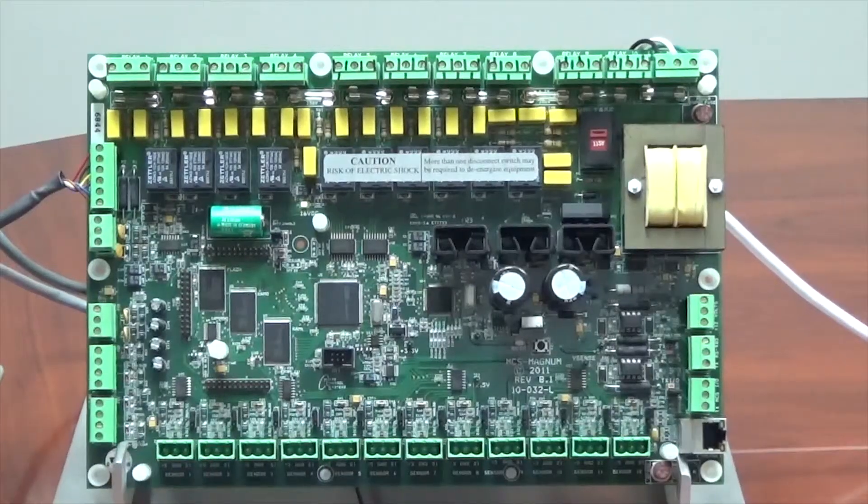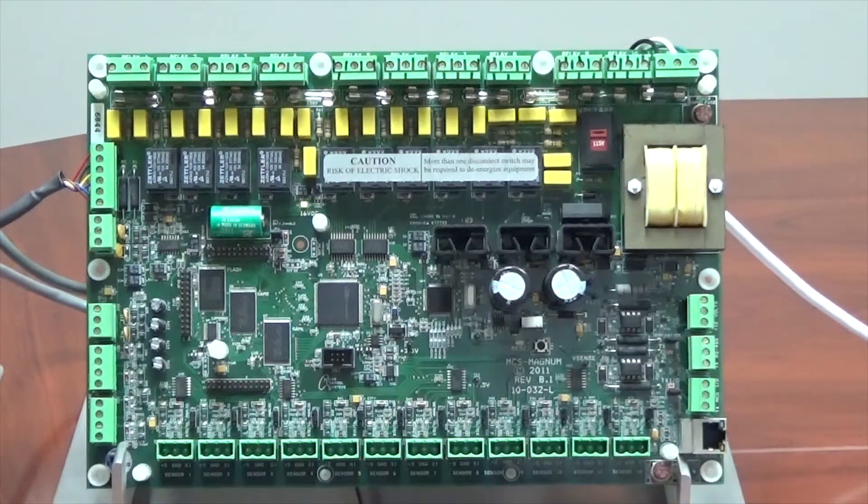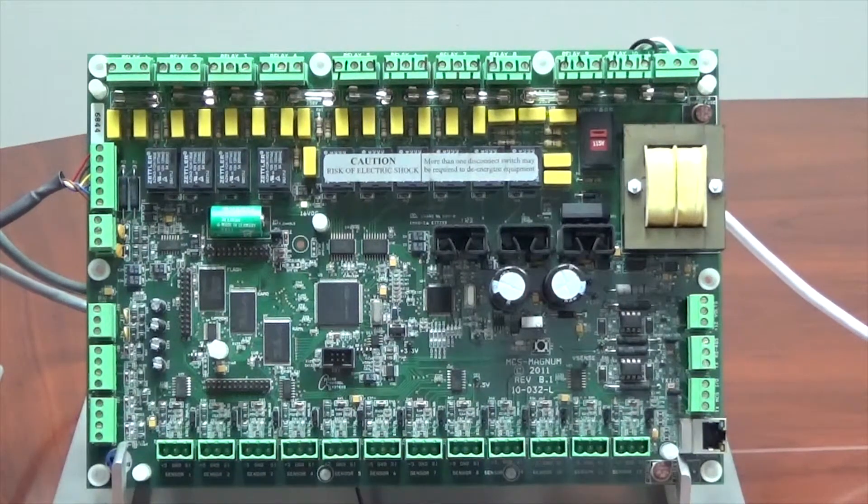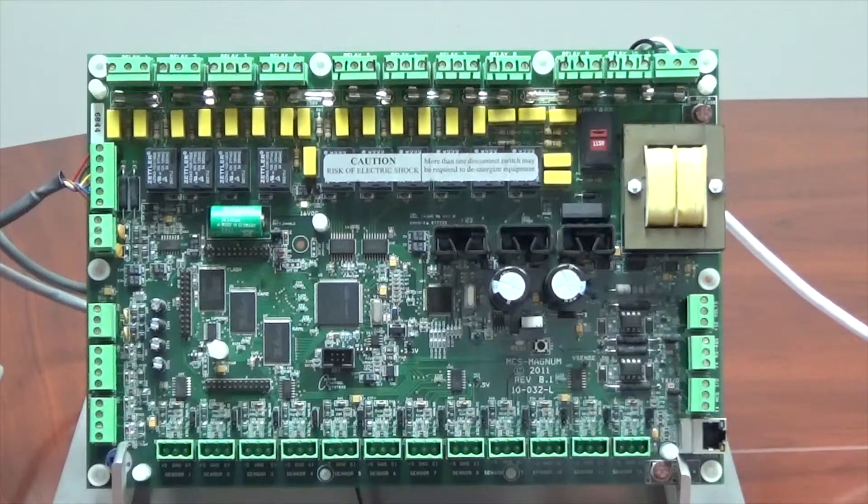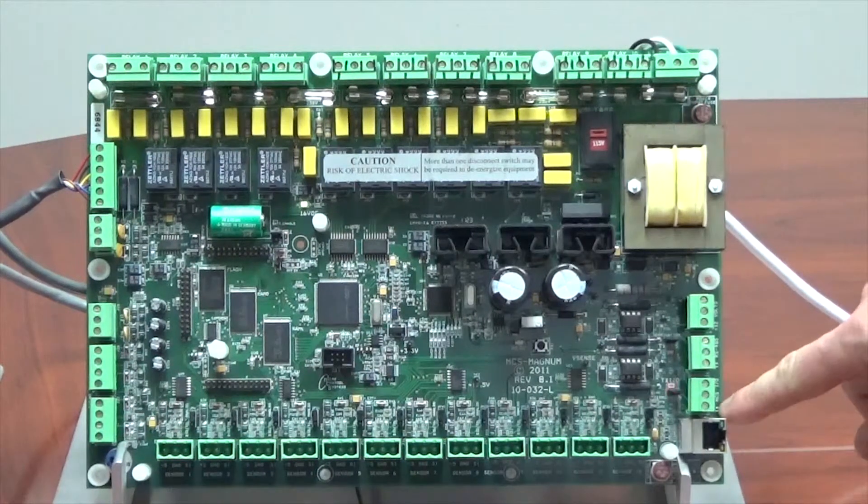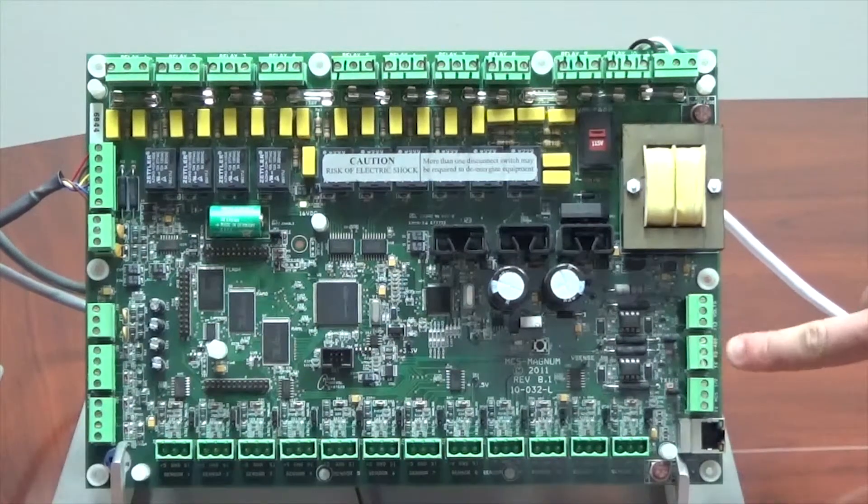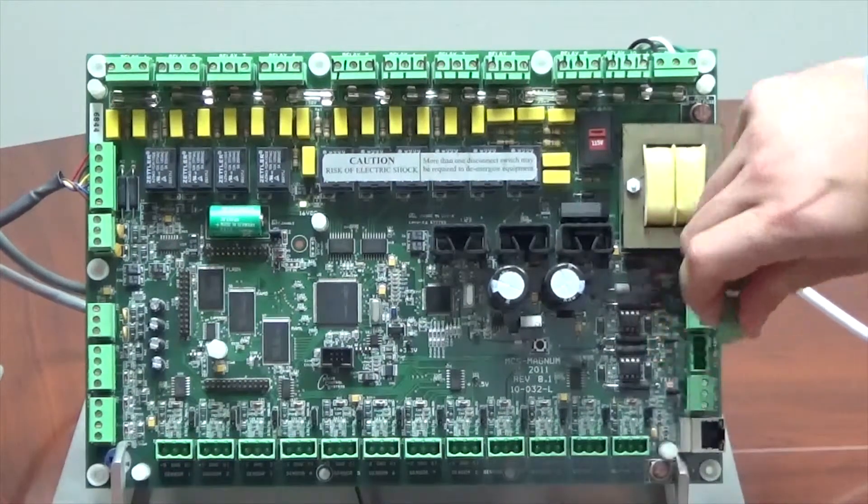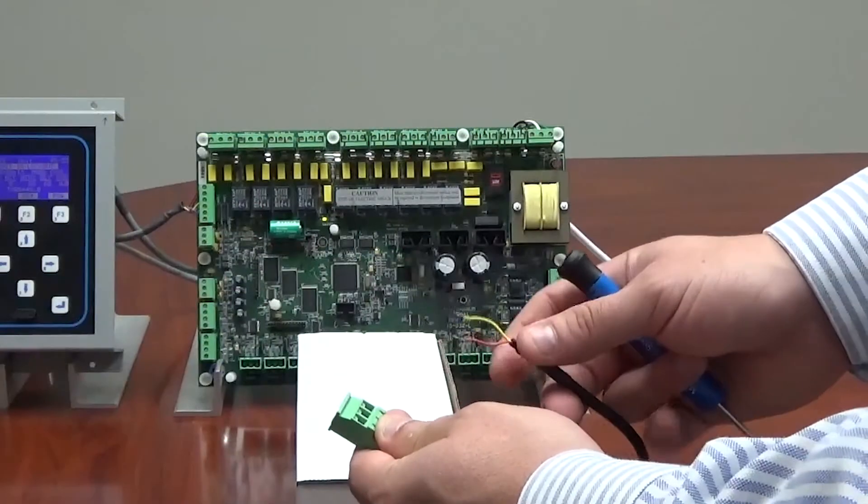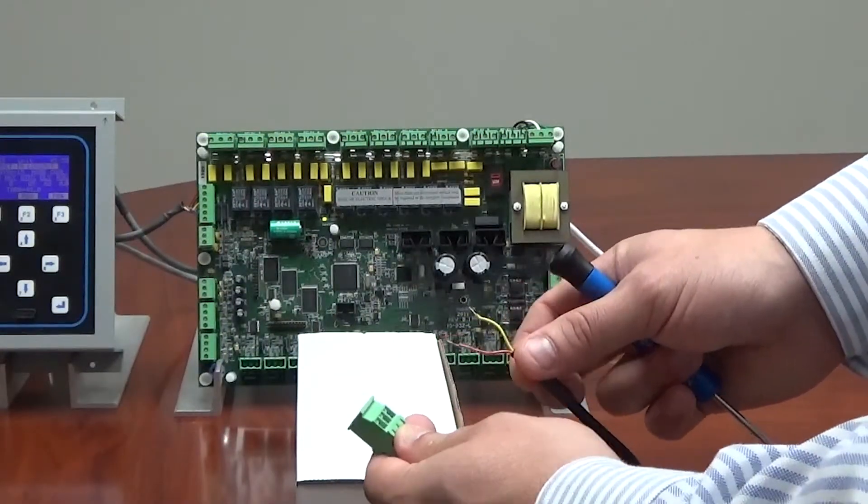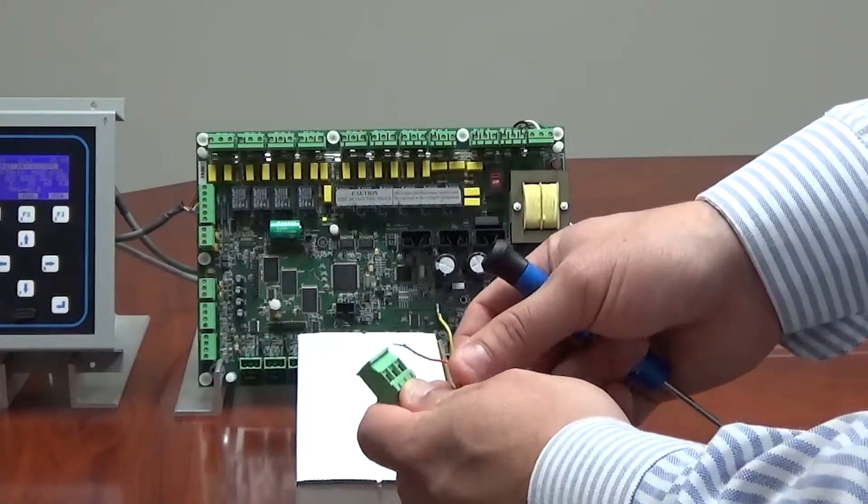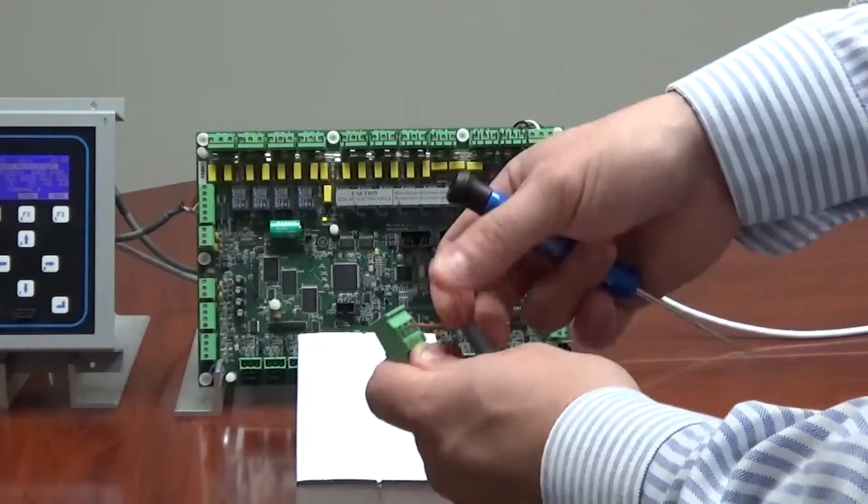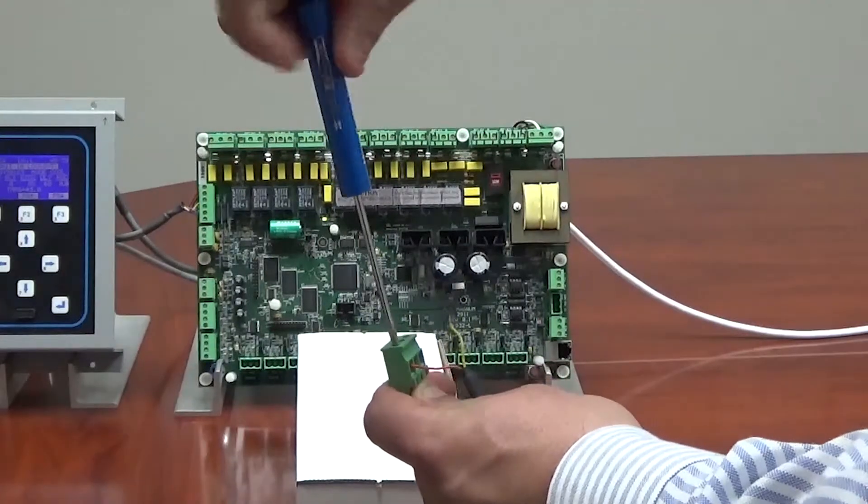This adapter will be wired directly to the RS-485 port on the Magnum board. The RS-485 port is located in the corner next to the ethernet port on the Magnum, and it's the second three position plug over from it. First remove the plug. We'll begin by wiring the positive wire to the terminal that's closest to the ethernet port on the Magnum.